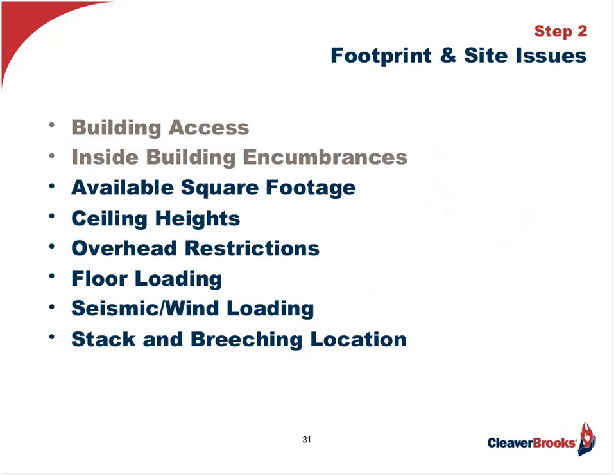Other footprint considerations include adequate space for walking around the boiler for maintenance such as casing and tube replacement or burner repair and adjustments. We need to look at ceiling height to accommodate boiler piping, valving, and an economizer. This also includes overhead restrictions such as ducting or pipe racks, and even Ethernet and communications wiring running to the boiler room. There's also the floor loading requirement — whether the floor is substantial enough to hold the weight of the new unit, where the pilings are, and what about seismic and wind loading. In this case we're using an existing stack, but a new freestanding stack would require wind loading analysis.